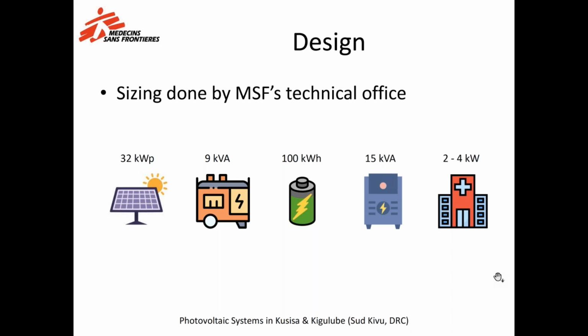This is one of the reasons for which we oversized the solar array. If we had done this system in another place, the solar array might have been a bit smaller, I guess. And also the charger inverter was also oversized because we wanted to have the capacity to adapt the system quickly in case the electrical needs grew beyond what we initially forecasted. That's why we went for this big charger inverter, but we soon realized that a smaller charger inverter of about 10 or even 12 kVA would have been maybe a better fit for these installations.